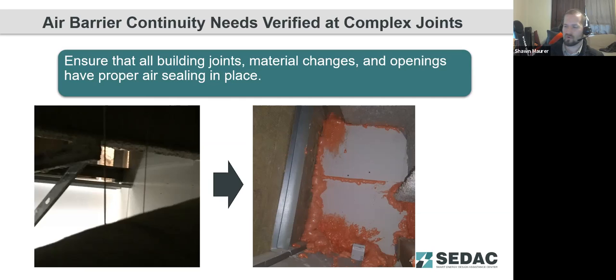On the other side of this wall is a covered patio with one of those perforated vented ceilings above it. The air barrier was supposed to wrap around that patio, aligned with the wall assembly. It's got a curtain wall assembly for glazing down below this area, and this is supposed to block off that open ventilated ceiling above the patio from the interior of the building. Right behind me in these pictures is an open plenum heat pump, so the return for that heat pump system is right here, facing this opening towards the outside.